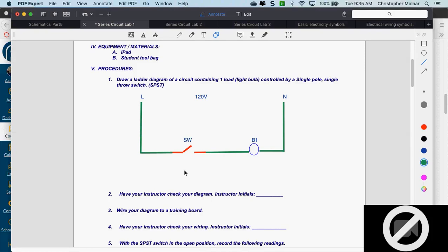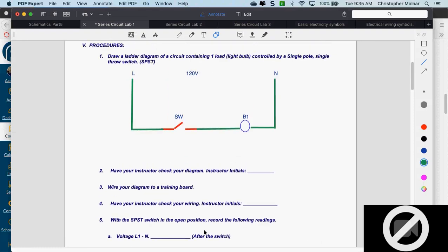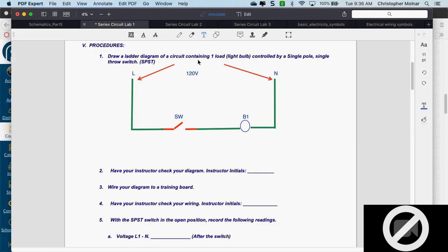The switch as drawn is open. If my switch is in the open position and I put a meter from L to neutral, I'm going to get 120 volts — that's the voltage across the source. If I don't get 120 at the source, there's no point going further in the circuit; you have a problem to start with.